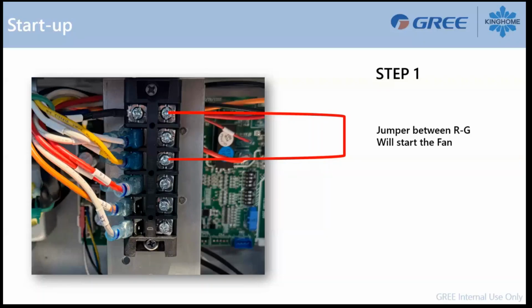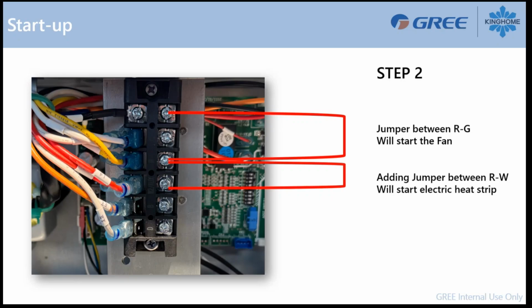When it's time to do the test, I suggest you put a jumper on your connection right away, between R and G, and start the fan. Make sure your fan motor is working properly. You have already adjusted the CFM with your dip switches, and you have taken your static pressure. So by using a jumper between the R and G terminals, that will start the blower motor. Then you can add another jumper on R and W, and that will start the electric strip.